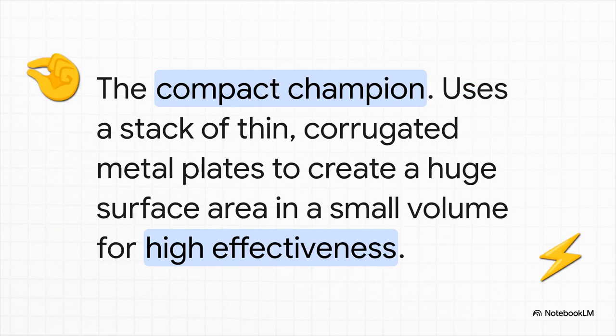And then you've got the gasketed plate exchanger. Instead of a bunch of tubes, this design uses a stack of really thin, corrugated metal plates pressed together. This creates a massive amount of surface area in a super tiny space, which makes it incredibly efficient at transferring heat. But that compact design comes with a totally different set of pros and cons.